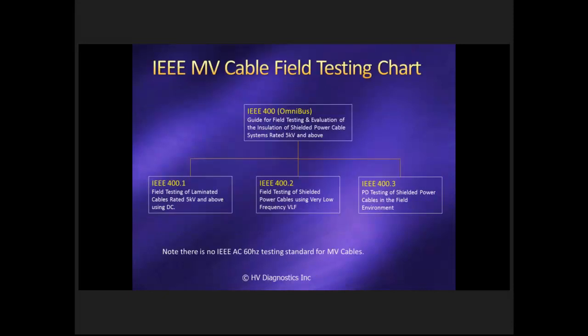If we look at the IEEE standard, and I would encourage some of you to go and have a look at the standards if you haven't, there's an IEEE 400. There's a brand new revision of the 400 standard that came out in June this year, and that's got a lot of very, very good information in it. It's a real improvement on the original 400 document. There are some really good guidelines as to what methods should be used when in that document. And then the sub-documents under 400, which is kind of the parent document, is the 400.1, which is for DC testing of paper-lead cable only, not for extruded cable.